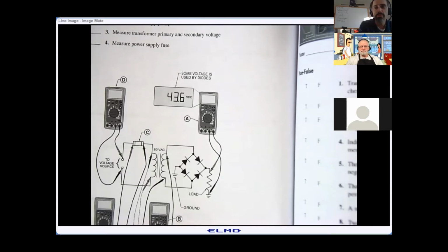I'm going to start visually, before I even put a tool in there, I'm going to visually look at that board to see if I see anything. I said I smelled something. Could be a couple of different things going on. If I have some inductors, I could have some inductors that could have cooked up on me in there too. So the first thing I'm going to look for is a discoloration. Also, I'm going to see if there was any black on the frame. That is an indicator that you had an arc flash in there. And also, I'm going to look at all the caps. If I see any caps that are bubbling up on top, or that are blowing apart, then I know something has happened to those caps. So those are the things I'm going to look at visually.